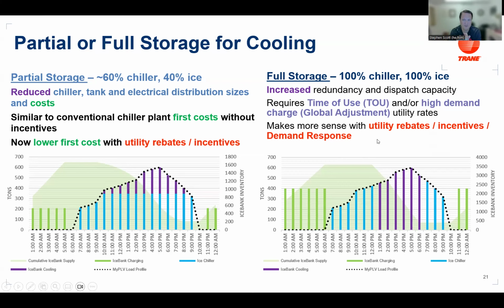The other one we looked at, again depending on utility and rate structure and your business, is full storage. This requires more cost because you're not downsizing the chiller, you're keeping it the same size, but you're sizing your off-peak hours for full storage. This can be more advantageous for customers with high time-of-use rates, maybe impacted by the global adjustment charge, or discussing with the local utility how they can enable demand response. So this doesn't necessarily have to be a full-size chiller plant taking everything offline, it could be taking a portion of the system offline as demand response—something like partial storage, or to the extreme, full storage.